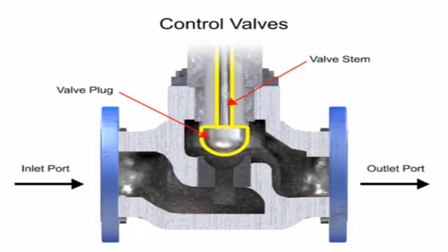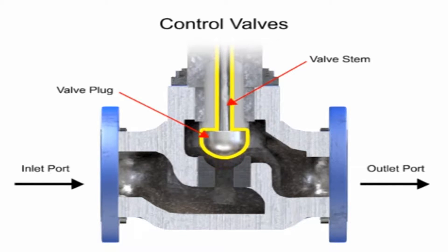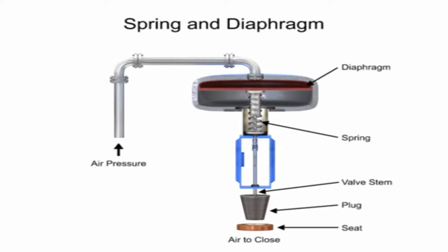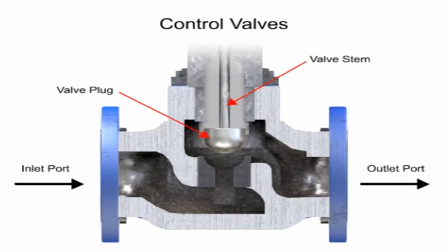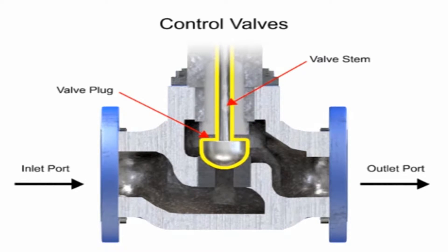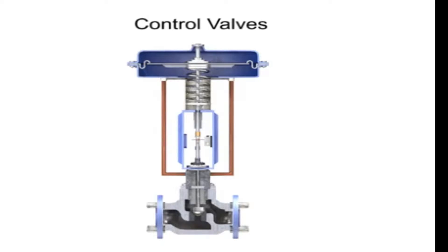This is the inside of a control valve body. The plug moves vertically up and down — it is a sliding stem control valve. You give the instrument air pressure through the tubing; it enters into the actuator diaphragm. This diaphragm is made up of nitrile rubber. And then it pushes the spring, which in turn pushes the valve stem downwards and upwards depending upon the air pressure. The plug moves up and down to allow the process fluid from upstream to downstream. This is how the control valve controls the process fluid.